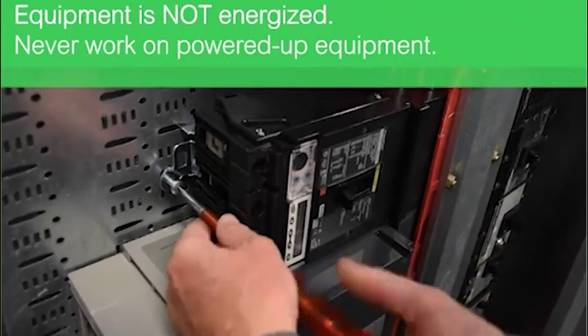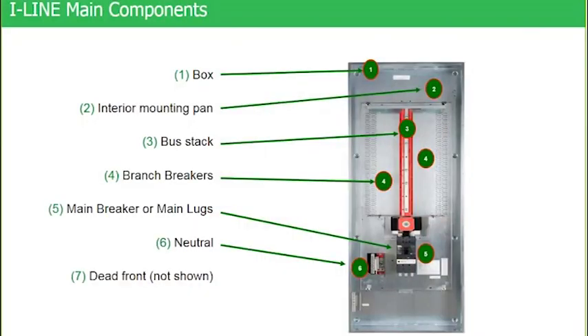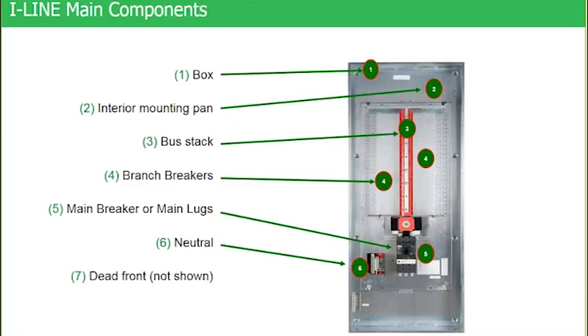If you look at number five, this is what we call a vertically mounted main breaker. That main breaker is vertical to the bus stack. In some cases it actually plugs on to the bottom of the bus stack if it's bottom feed. Or in other cases it utilizes what we call a t-bone connector, which is a small bussing connector that then bolts into the bus stack.